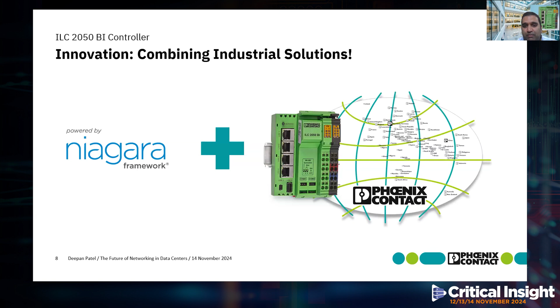Well, one key point is that 63 IO modules can be connected to one single controller, making it a unique controller to help control your data center demanding high outputs and inputs. So dense, high number of outputs, for example, it can fit up to 63 modules, and that could be a 32 channel input module times 63.